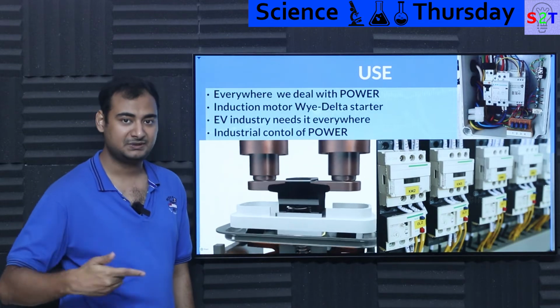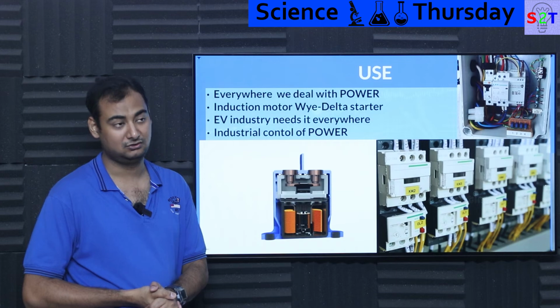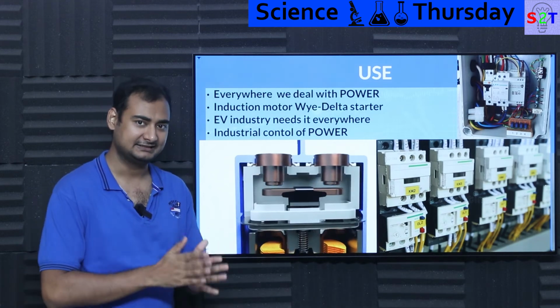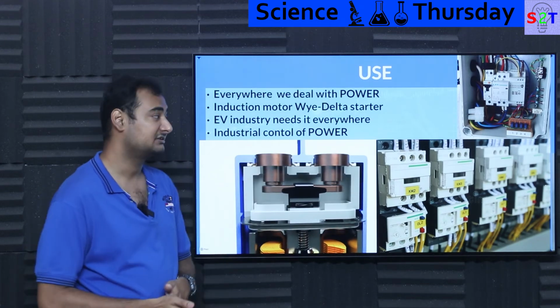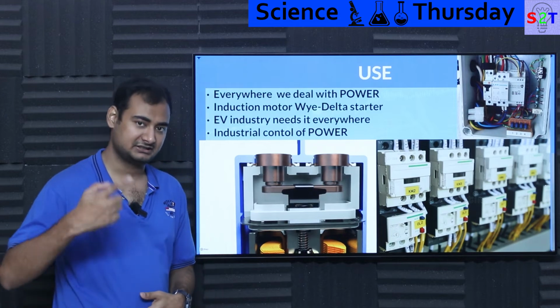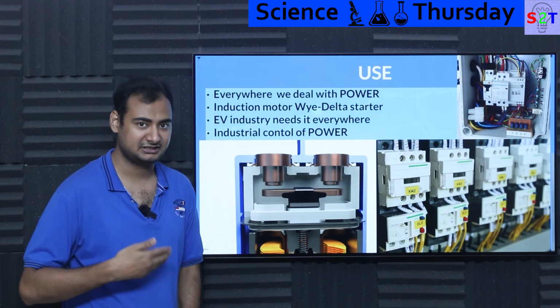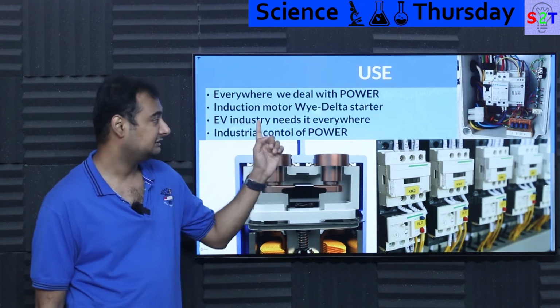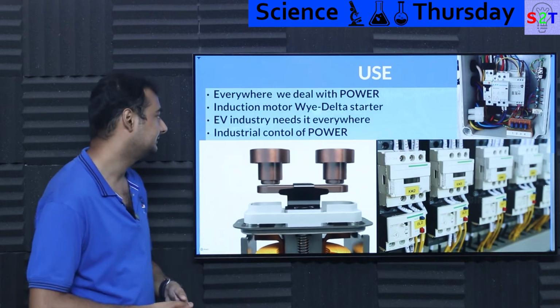Once the motor has spinning momentum, depending on the load, the programmer will set it to stay in Y configuration for 5 or 15 seconds. If it's very geared down, it takes time to spool up, so it waits, then switches to delta, which is far more efficient.